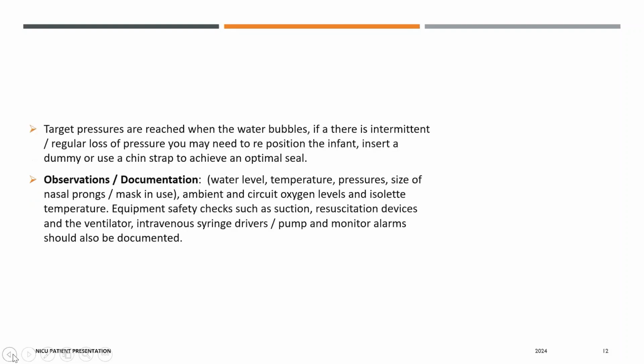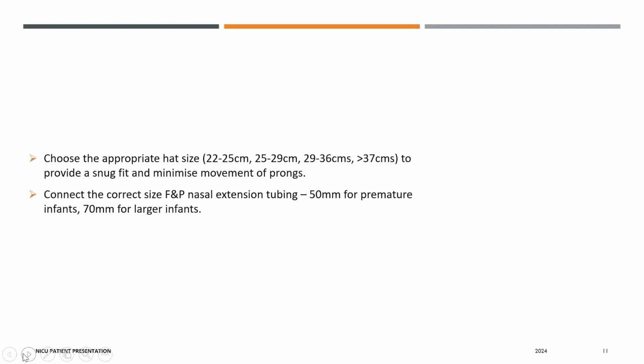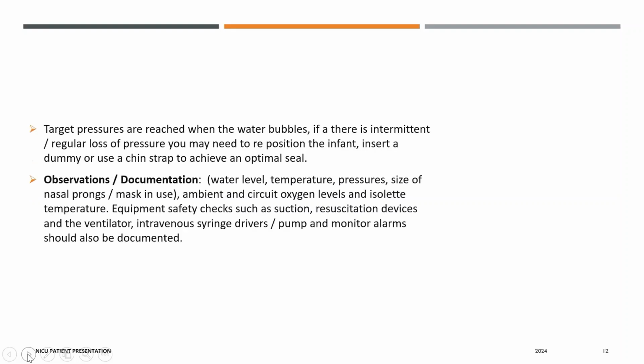Okay. Target pressures are reached. Next slide. Target pressures are reached when the water bubbles. If there is intermittent or regular loss of pressure, you may need to reposition the infant, insert a dummy, or use a chin strap to achieve an optimal seal.